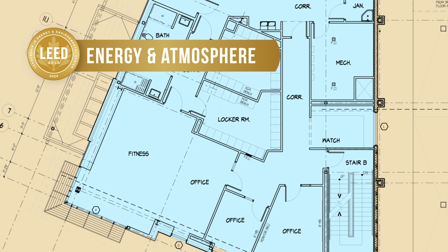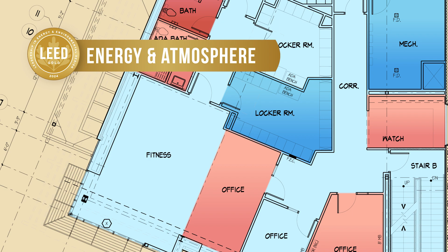Another feature that contributed to our LEED optimized energy performance is the use of smart thermostats. Connected to the building's automation system, they allow the facility manager and occupants to set different temperatures within different spaces. In this facility, the temperature can be set differently for the sleeping quarters, living quarters, office spaces, and more. This allows us to reduce the need to heat or cool spaces when they aren't being used, or to heat or cool spaces only when they're in demand, which contributes to a more energy efficient building.